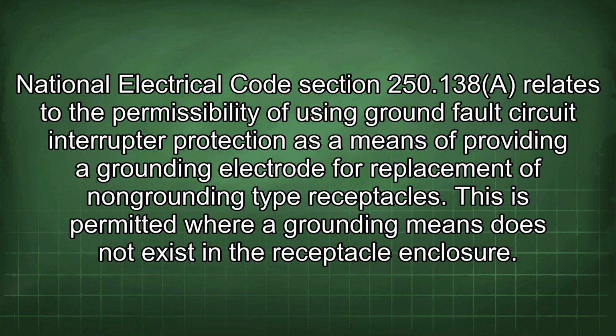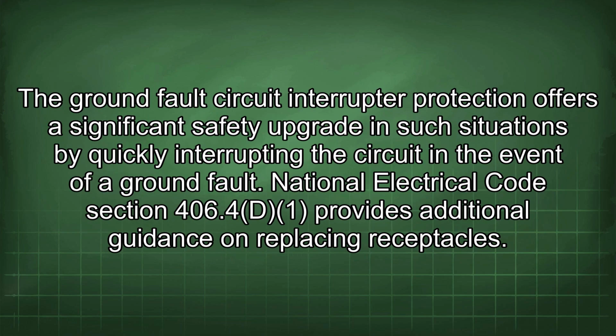National Electrical Code Section 250.138 relates to the permissibility of using ground fault circuit interrupter protection as a means of providing a grounding electrode for replacement of non-grounding type receptacles. This is permitted where a grounding means does not exist in the receptacle enclosure. The ground fault circuit interrupter protection offers a significant safety upgrade in such situations by quickly interrupting the circuit in the event of a ground fault.